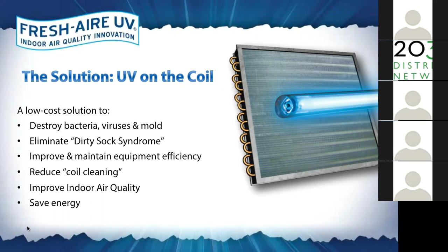But it's a very low cost solution to eliminate bacteria, viruses, and mold in this cold, dark, wet place. And because it reduces coil cleanings, you won't be paying as much in maintenance every year to keep your coil clean. And again, because it keeps the biofilm off the coils, you actually get much improved efficiency. So anyone that monitors their equipment should absolutely put UVC lights in, and you'll see that actually the return on investment is as little as 1 year.